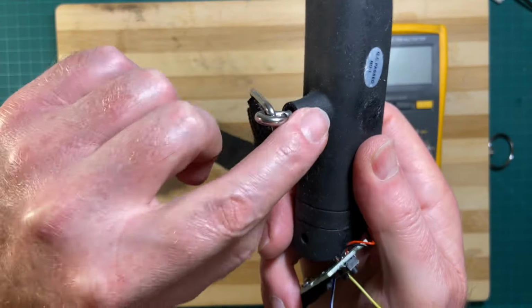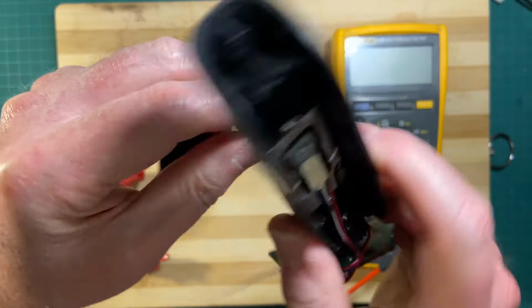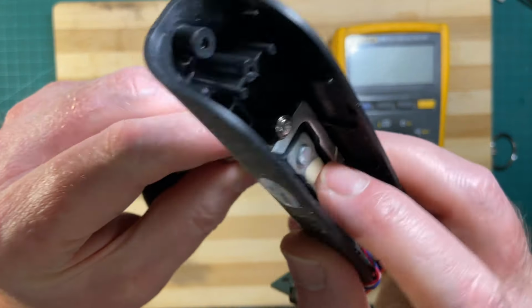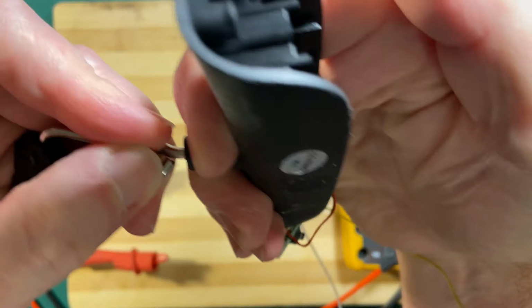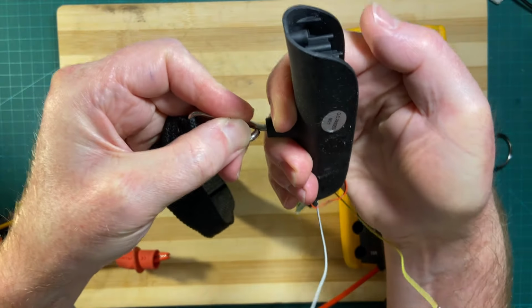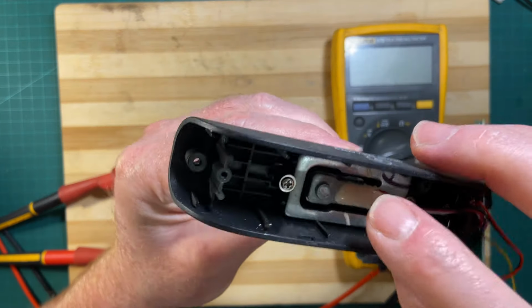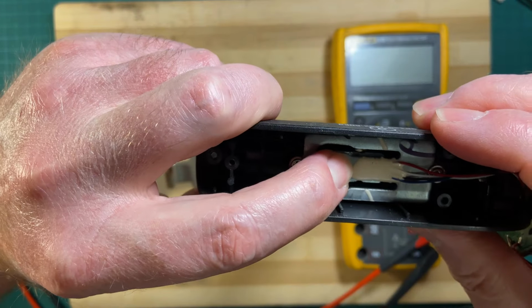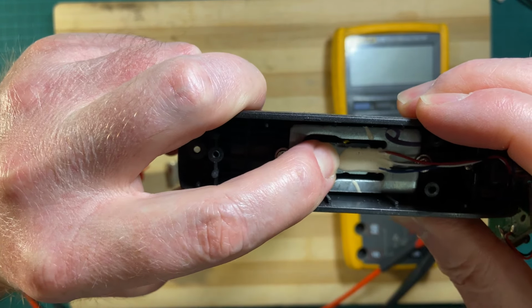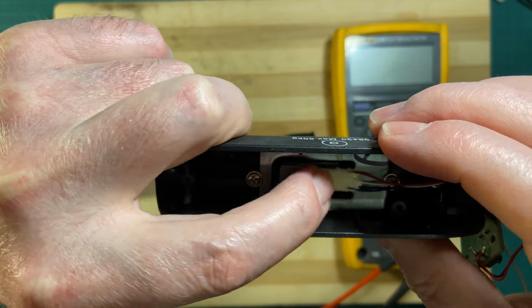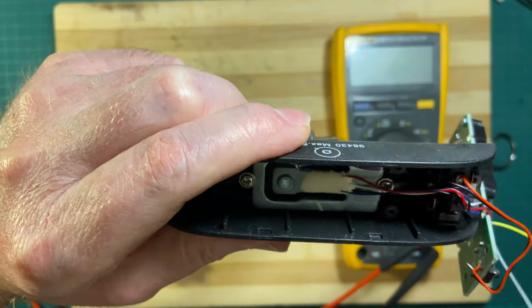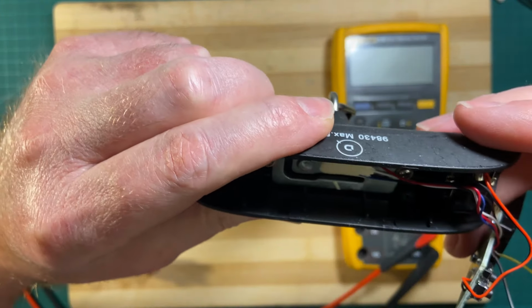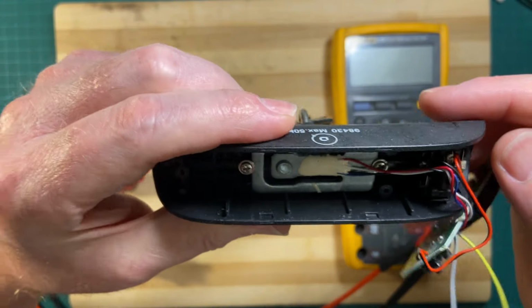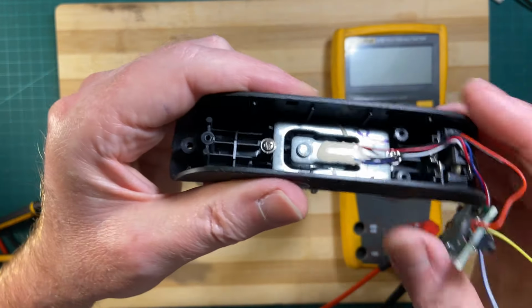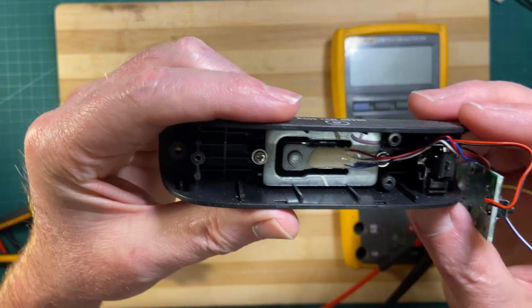So this goes through a hole, no contact there. So when you pull on this, because it works like this, it flexes this beam downwards like that, and it stretches the resistor in the Wheatstone bridge and changes its resistance, then you get a reading.